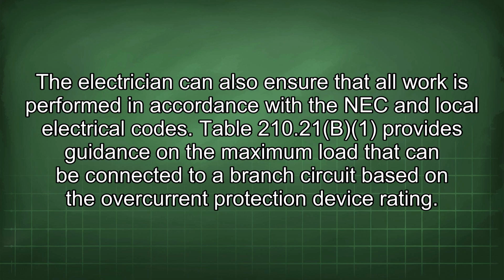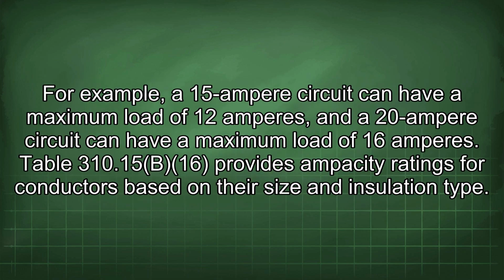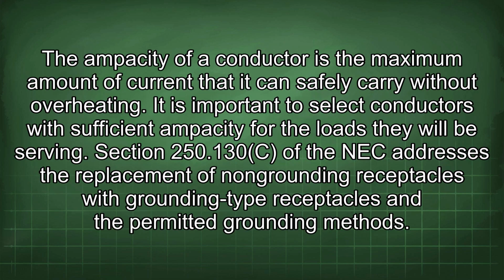Table 210.21 provides guidance on the maximum load that can be connected to a branch circuit based on the overcurrent protection device rating. For example, a 15 ampere circuit can have a maximum load of 12 amperes, and a 20 ampere circuit can have a maximum load of 16 amperes. Table 310.15(B)(16) provides ampacity ratings for conductors based on their size and insulation type. The ampacity of a conductor is the maximum amount of current that it can safely carry without overheating. It is important to select conductors with sufficient ampacity for the loads they will be serving.